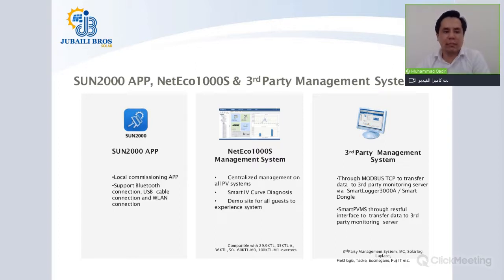Sun 2000 app, NetEco, and third-party management system. The Sun 2000 app is used when you are using the USB WLAN adapter for local commissioning, and also for firmware upgrade of the inverter, to know the current status of the inverter, or if there is an alarm, what the alarm status is, and that's all.